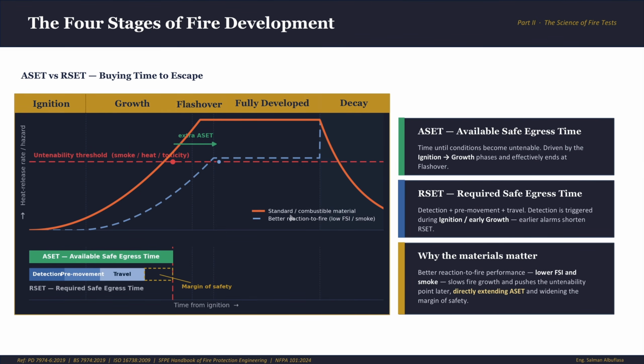The second clock is RSET, the required safe egress time. That's the time we need, and it's made of three pieces. Detection phase: how long before the alarm notices the fire. Pre-movement: the hesitation where people finish what they're doing, look around, decide if it's real or not. And then travel, actually moving to the exit. These three together, that's how long evacuation really takes.